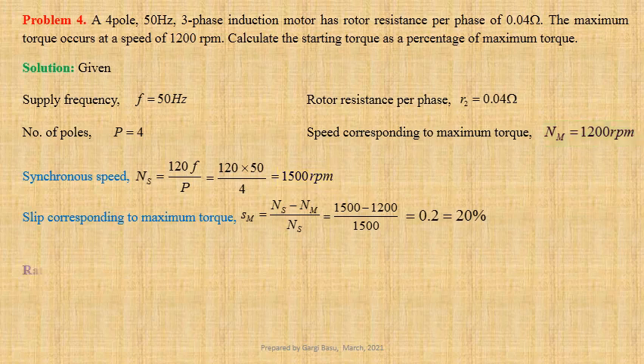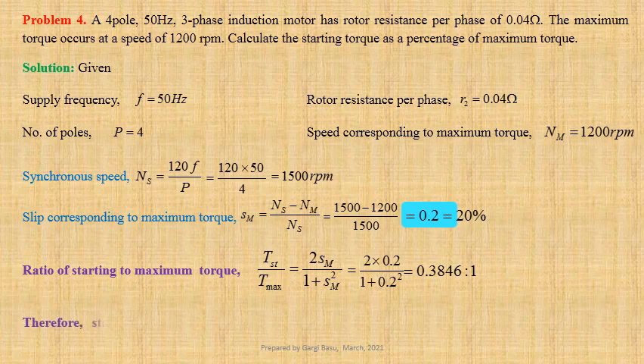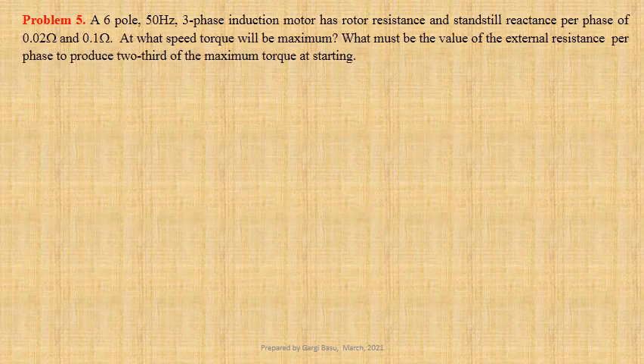Expression for ratio of starting torque to maximum torque TST is to Tmax equals 2 SM divided by 1 plus SM squared. Using value of SM we get 2 into 0.2 divided by 1 plus 0.2 squared, that gives us 0.3846 is to 1. Therefore, we can conclude that starting torque is 38.46 percent of the maximum torque.